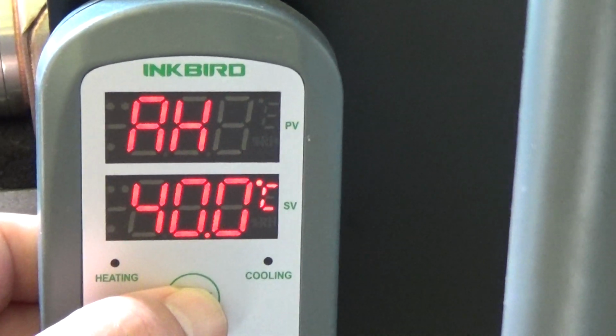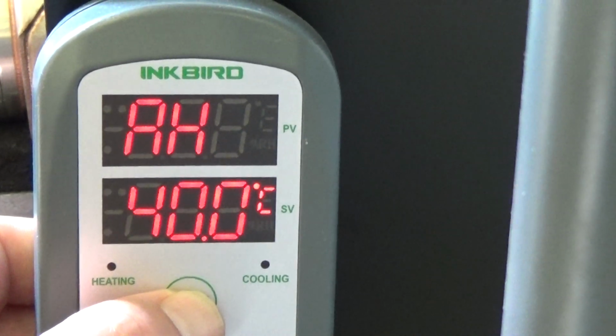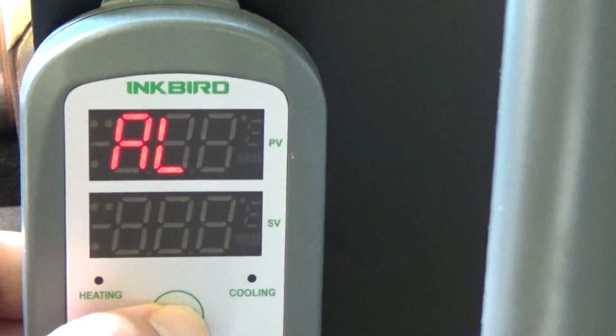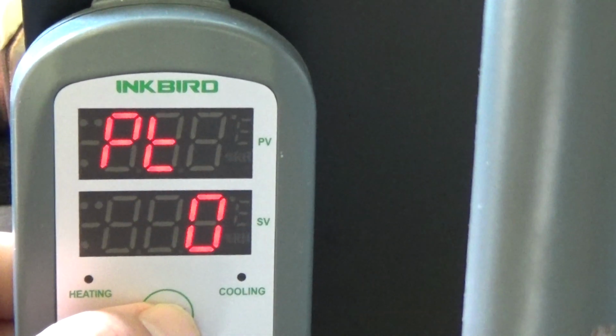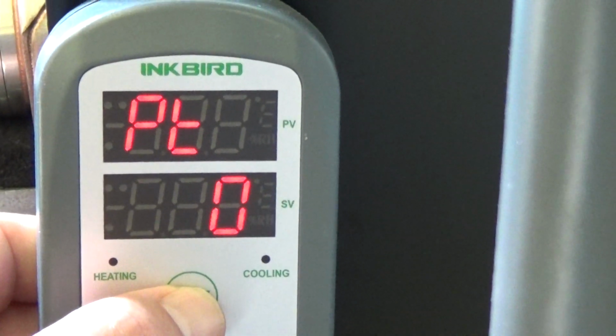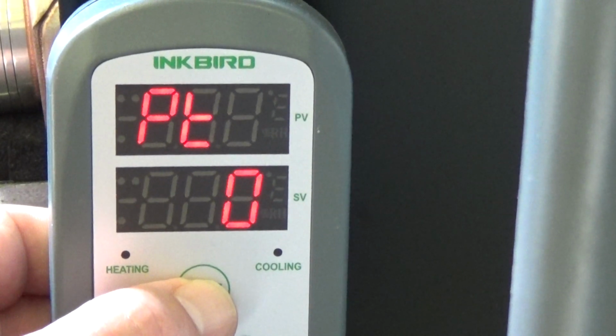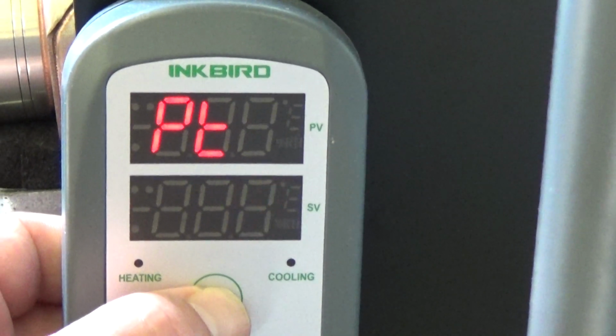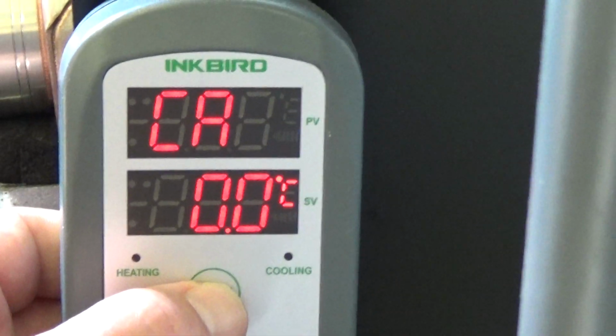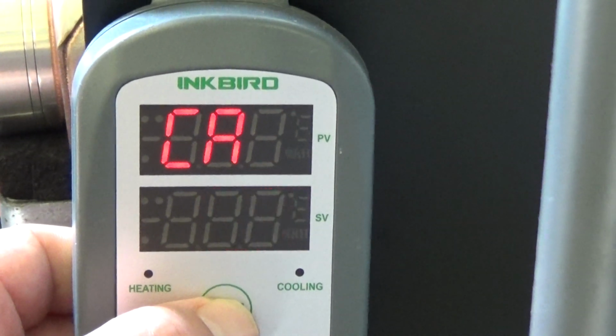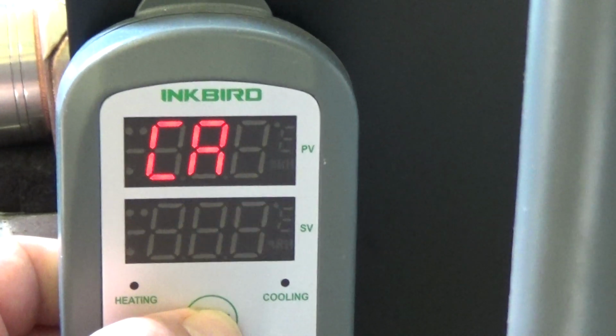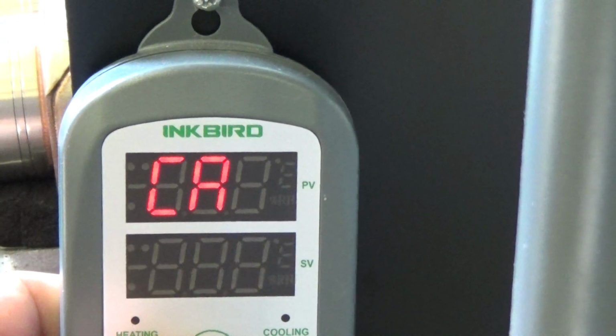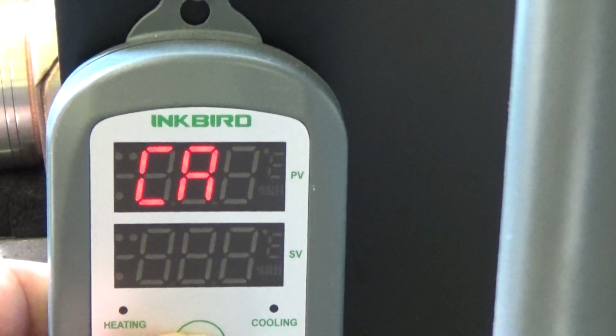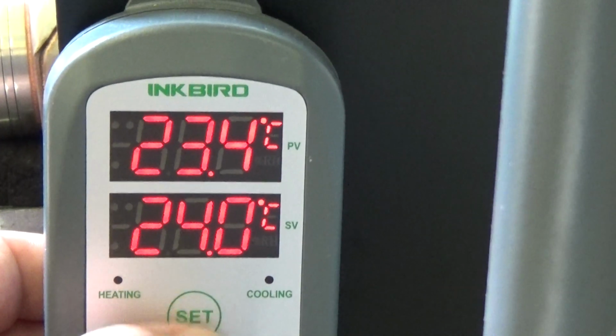Alarm high limit, there's a little audible alarm we have at 40 C. Low limit we have at 10 C. PT is if this thing was controlling a compressor, which it's not. That's a compressor delay, so that's not applicable. CA is calibration, if you want to go plus or minus in calibrating the temperature, if it's off a little bit. And then we just get back to our main screen.